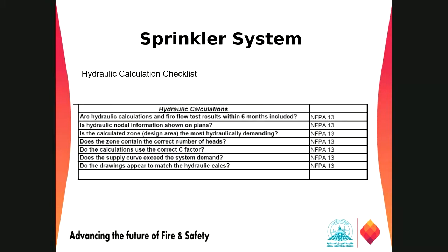And then we look, is the calculated zone design area the most hydraulically demanding, right? We have to look for that information. Normally in multiple hazard areas, we have multiple sprinklers and multiple hazards. It might be that the most hydraulically remote area is not the most demanding one. We discussed this in the fire protection design, so we have to keep those things in mind.